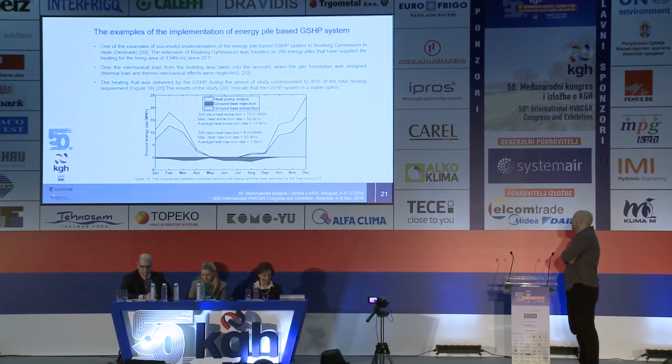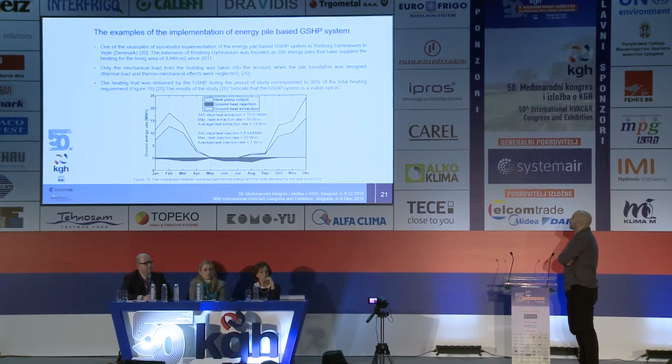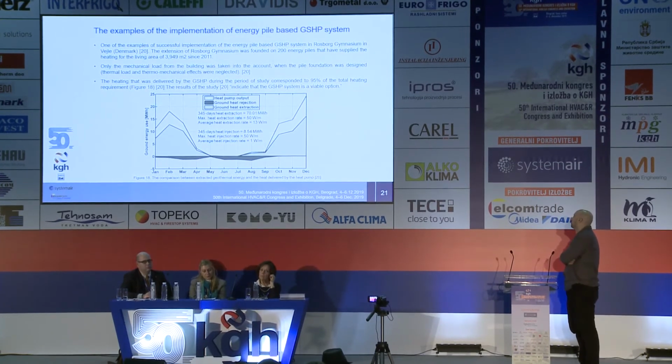So, anyway, at the end of the study, the authors have concluded that heating that was delivered by the GSHP system during the period of the study corresponded to 95% of the total heating requirement, which is, I think we can all agree, pretty high. So basically the results of the study indicated that the GSHP system was a viable option.